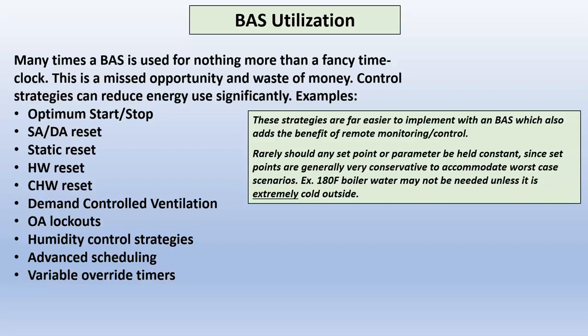Supply air and discharge air reset. I got a graph on that too, but basically, most places are designed at 55 degrees supply air temp out of an air handler or a rooftop unit. I really don't need that when it's cold outside. So what this does is allow me to save energy and raise that temperature. Actually, I adjust that temperature based on the needs of the facility and the outdoor air temperature.